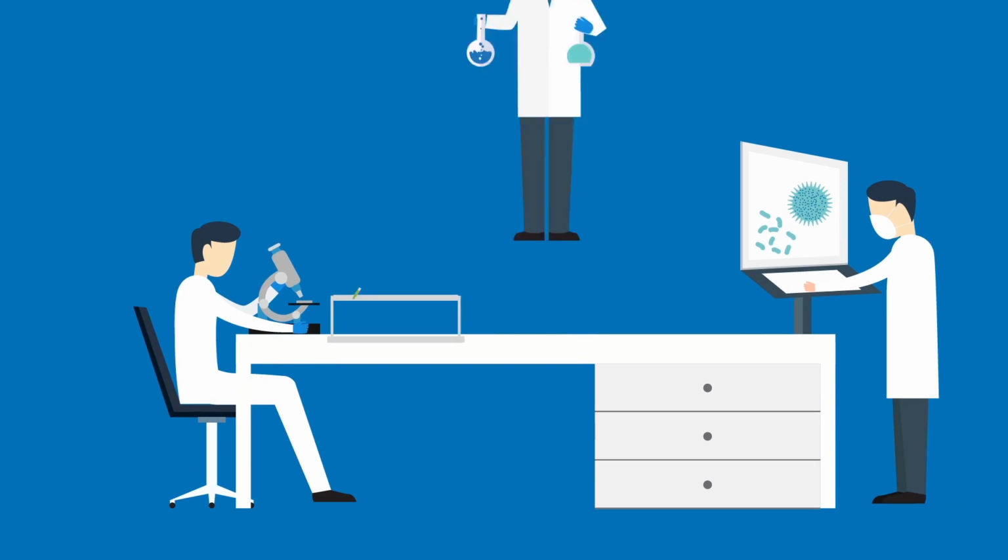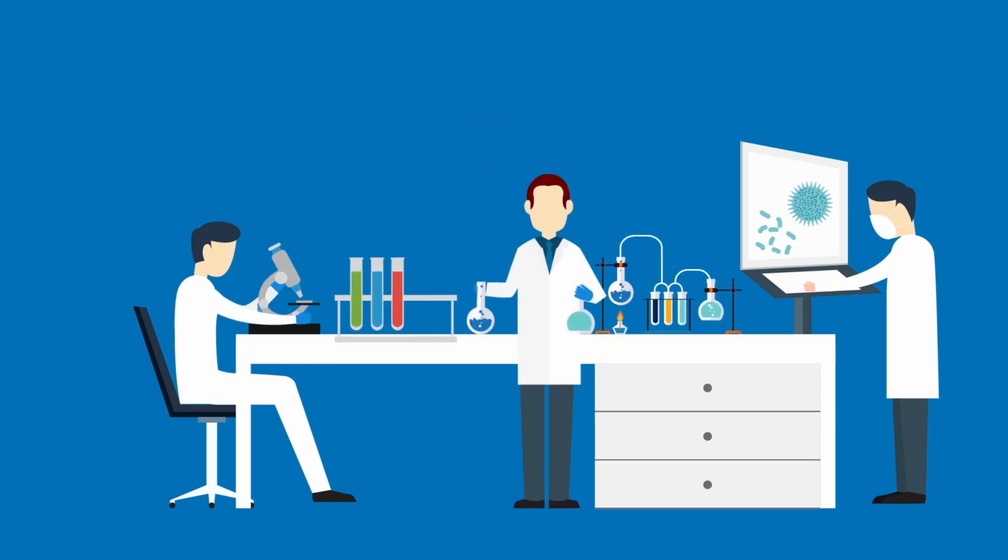In the EU, the person responsible for establishing if a product is a medical device is the legal manufacturer. The legal manufacturer is named on the device label, and it is they that establish the device's intended use. The legal manufacturer is held responsible for the device, regardless of whether they have designed and manufactured the product.